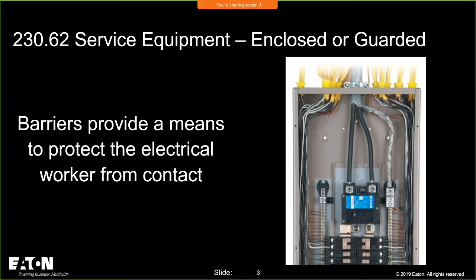And it continues the journey of what happened in the 2017 code with regard to 408.3. Remember, in 408.3, they added one word, panel boards, to that section of the code, and all of a sudden service entrance panel boards had to have barriers on that line side, and so that expanded. That was a requirement that was just panel boards and switchboards and switchgear. But what happened in this cycle was they said, what about the switches? What about transfer switches? What about a motor control center that's service entrance rated and all of this other equipment? So they've expanded that barrier requirement.